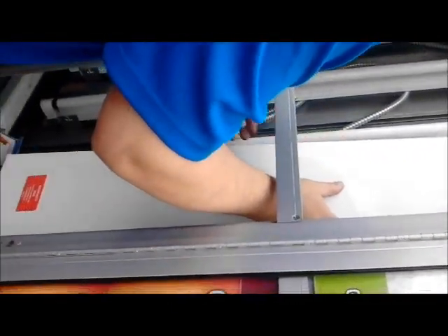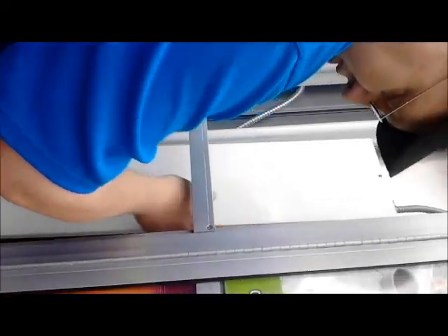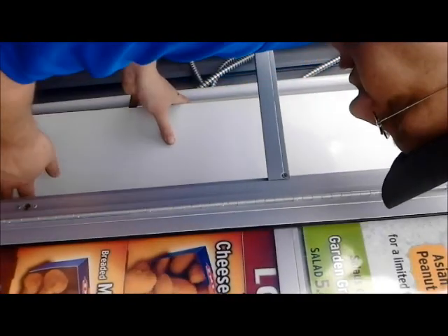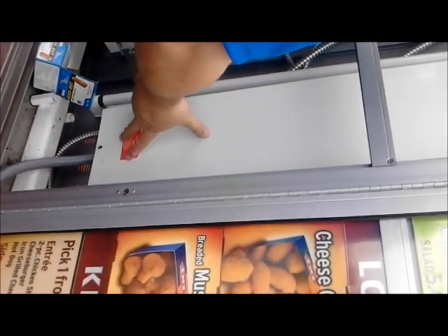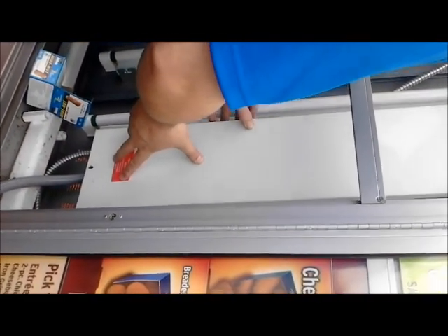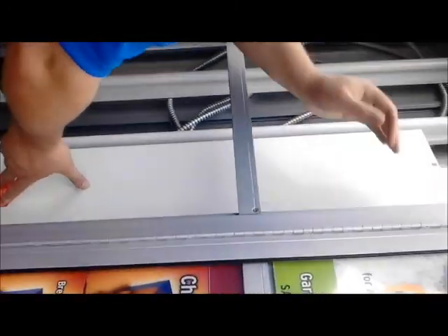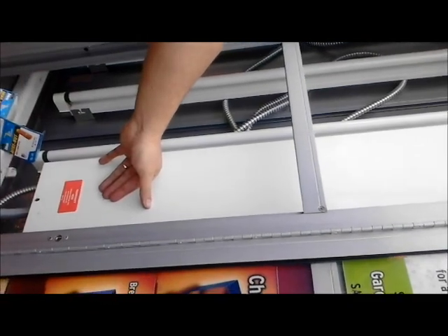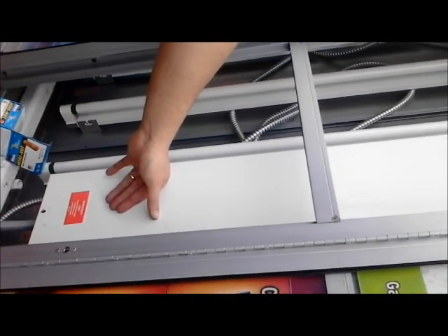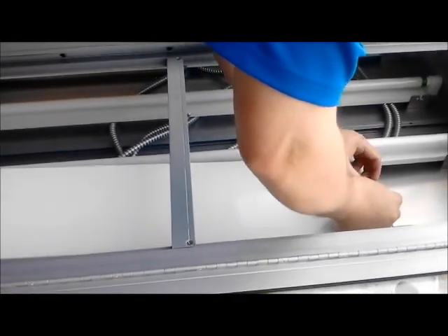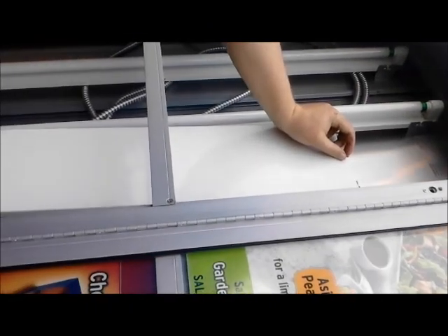Now, we're going to take the panel and try and get this in. Just make sure you don't pinch any wires on the frame here. That's the huge deal, is you don't want to pinch any wires, because generally it'll be rubbing against the metal frame, and if you have any sort of vibration on your equipment, it'll sever through an arc, and that can also be a bad situation in terms of causing fires, that kind of thing.